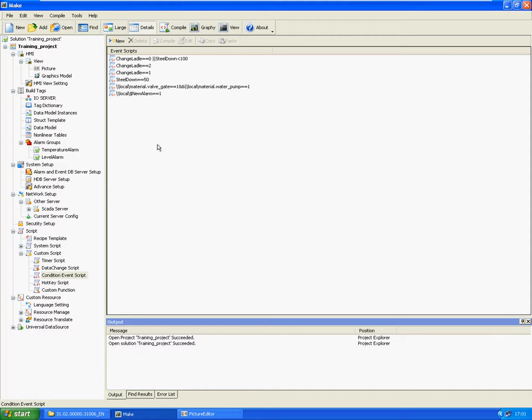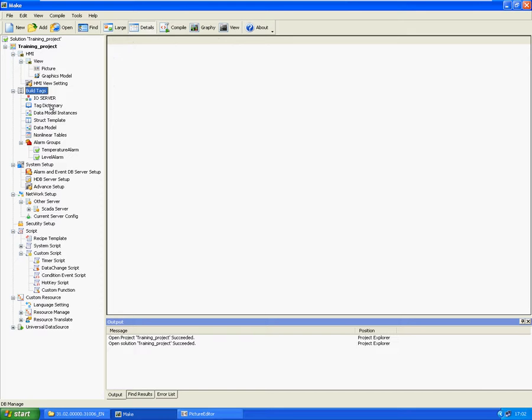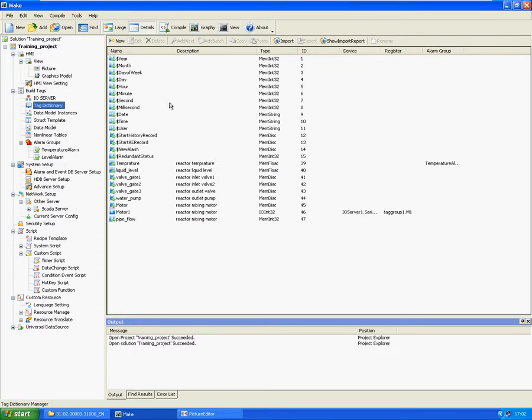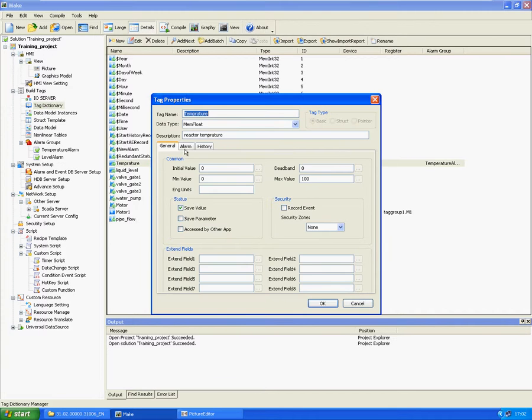The property of record event should be defined first, and then the operate event can be generated. The definition process is as follows. Step 1. Double-click a tag in the tag dictionary of Kingscada, and then you can set the properties of the tag in the dialog box that pops up. Select the checkbox of record event in the general tab.